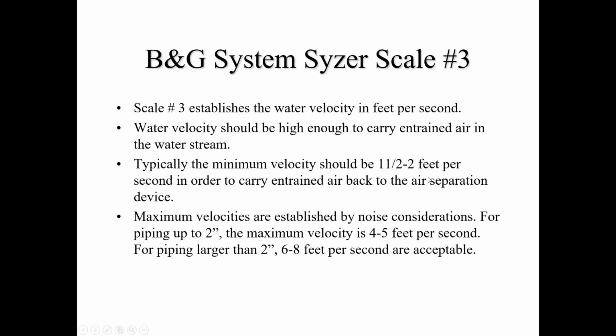A couple of quick rules of thumb. Water velocity should be high enough to carry any air bubbles, small entrained air that might be out in the system. We want a minimum velocity, typically 1.5 to 2 feet per second. We don't want to get below that for air movement. On the high side, maximum velocities will vary, but if you're doing a closed loop hydronic system, chilled water or heating, and noise is a concern, such as a classroom, an office, a home, an apartment complex, or a hospital, where there are people in these rooms, there's a certain max you want to abide by.